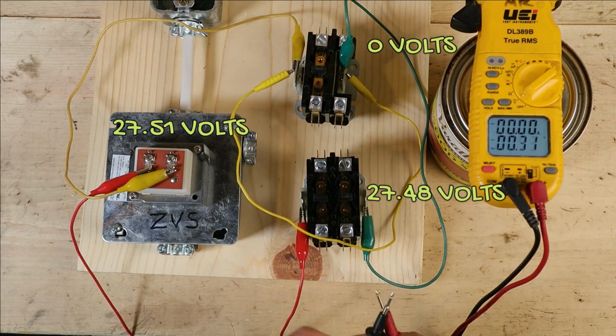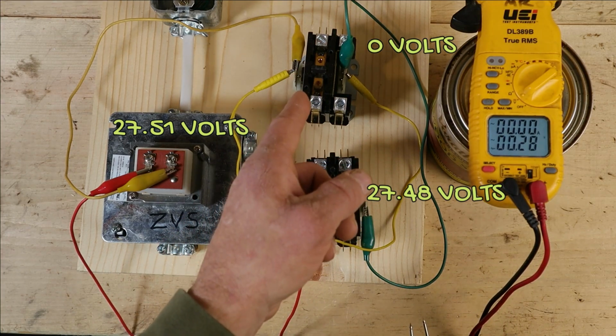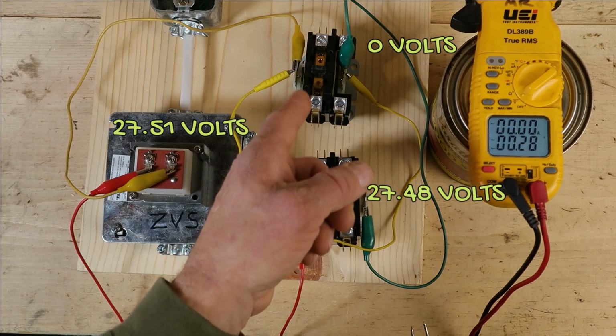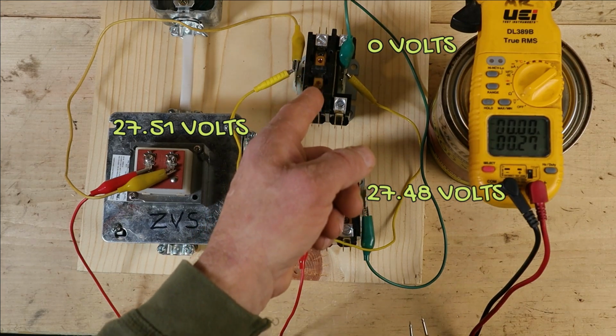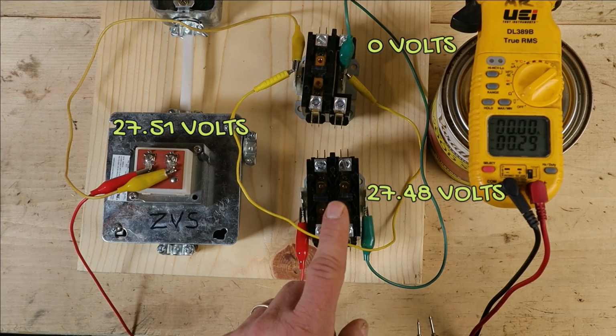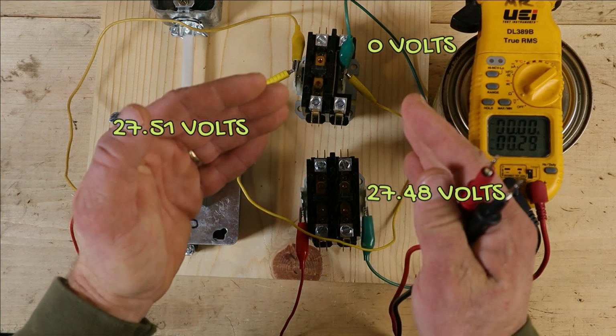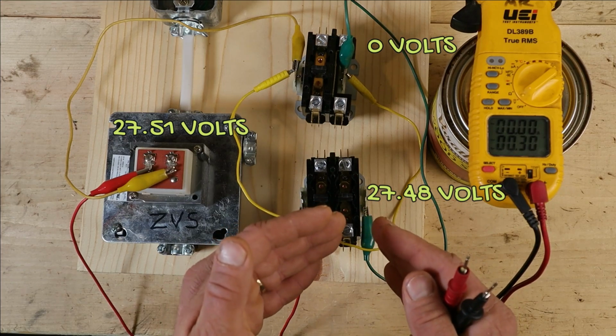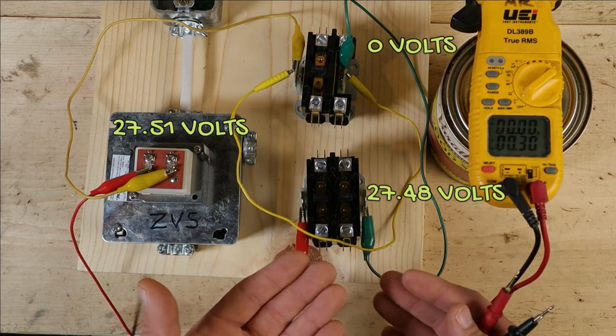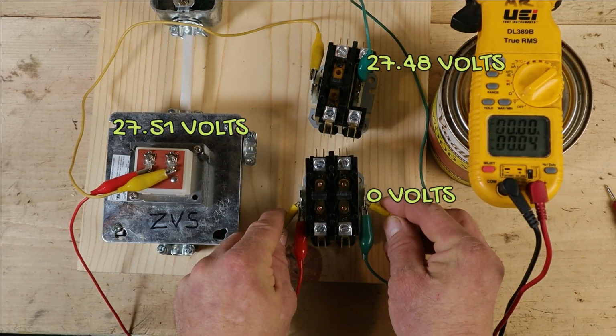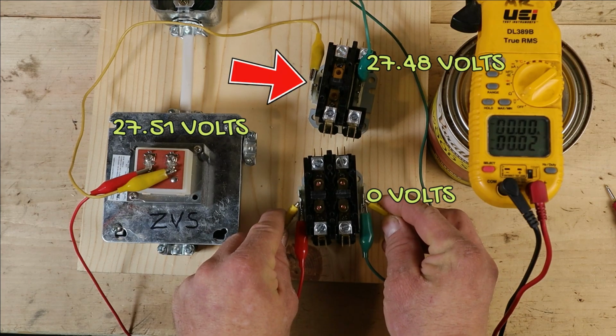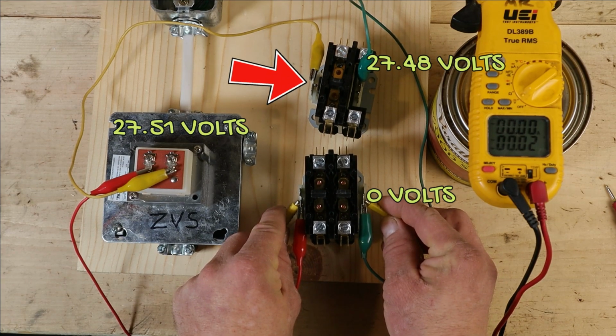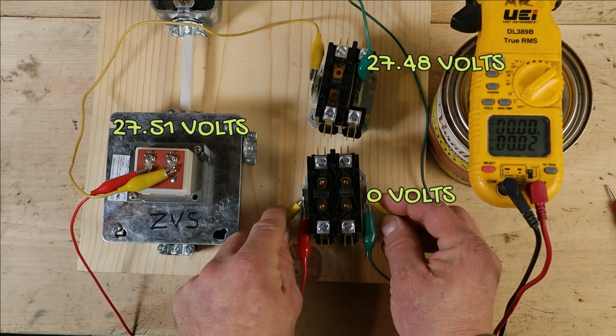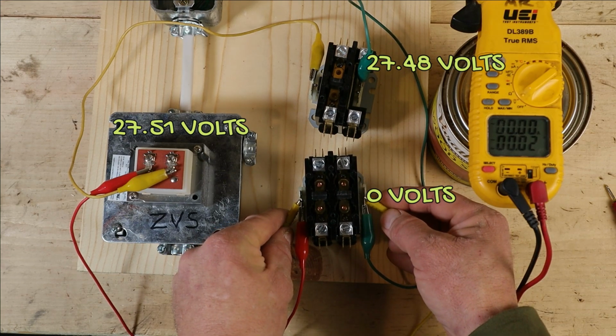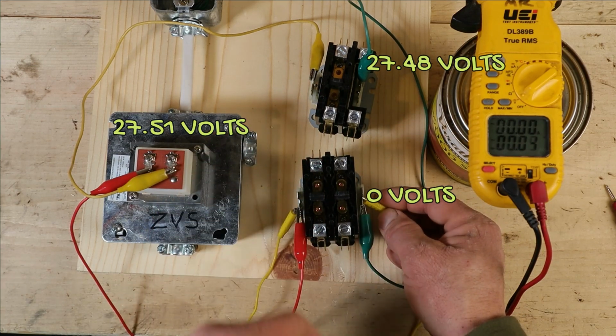So what's going on? By giving the electricity a path of zero resistance, I essentially took the resistance of that coil out of the circuit. So the only resistance on the circuit now is in this contactor, and all the voltage was able to travel to that point of resistance, providing enough voltage to pull that contactor in. Now, if I take this jumper off and go to the other one, you can see this one opened up and my contactor number 2 reclosed. That is because I took the resistance of this coil out of the circuit by allowing the electricity a path of zero resistance, and now all my voltage is over here.